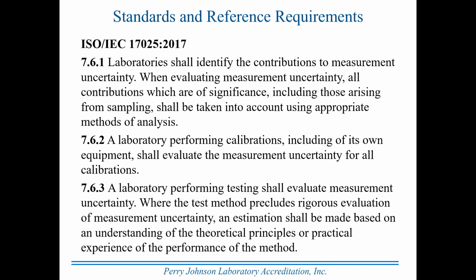Those would both be tests, and measurement uncertainty potentially would be handled differently for both because of the nature of the materials, the nature of the test itself, the nature of the environmental conditions under which the test is being performed. Testing is broader based in terms of how measurement uncertainty is addressed. Calibration is very specific. If you perform a calibration and report the results, you must estimate the measurement uncertainty specific and unique to that calibration.